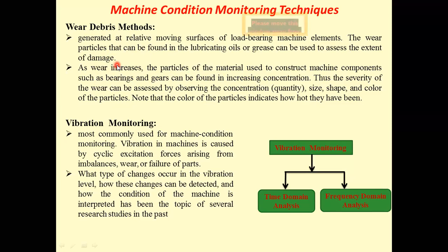Thus, the severity of the wear can be assessed by observing the concentration, that is quantity, then size of wear particle, shape of wear particle, and color of wear particle.